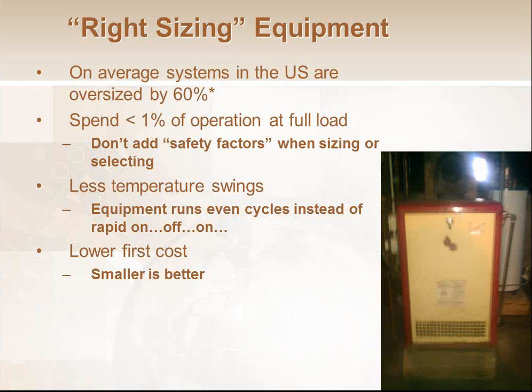So we want to get you to size it at least down, round it down, or resize the new plant for as big as the radiators are existing, because obviously they're covering the heat load now. And then if you do Manual J residentially or ASHRAE load calcs commercially, you can get even more aggressive with correctly sizing it. Eric asks if Illinois requires that we do a Manual J load calc for every new boiler installation.